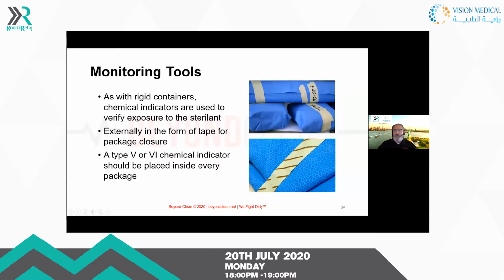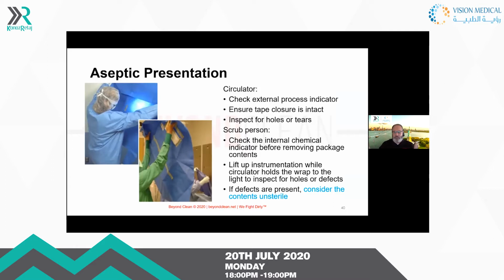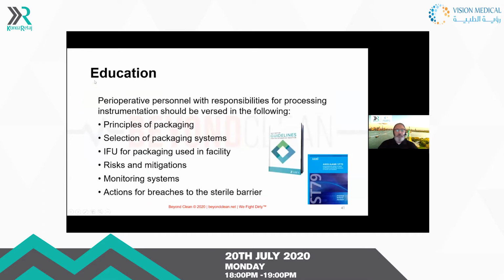And in this upper picture, you want to always make sure that you're following the manufacturer's instructions for use. This set that was sterilized in 2006, I found on the shelf in 2017. And we know that the manufacturer of the blue wrap says that you cannot leave this on your shelving for more than 10 years. It will not maintain the integrity. When they're open, we want to make sure that they're being checked properly in the operating room theater, that the scrub person and the circulator understand that there are no holes, again, to ensure that we have the proper processes.